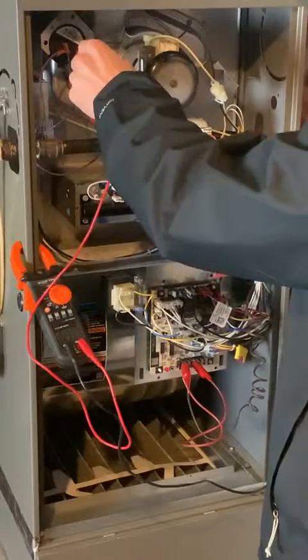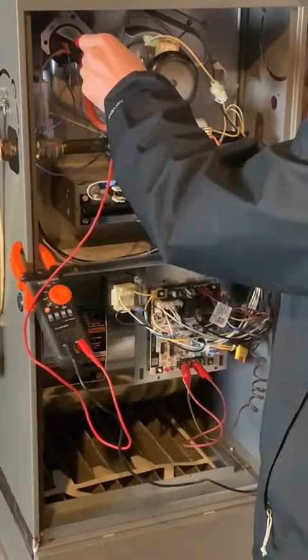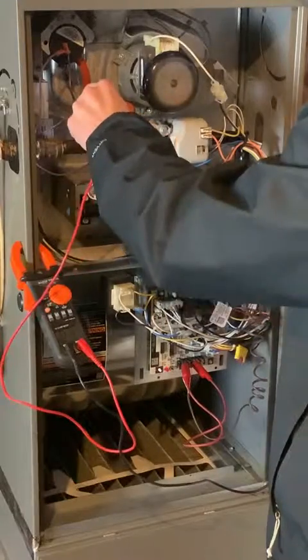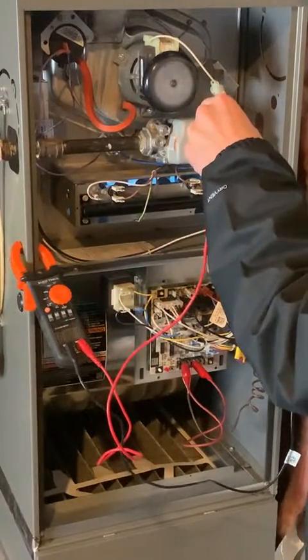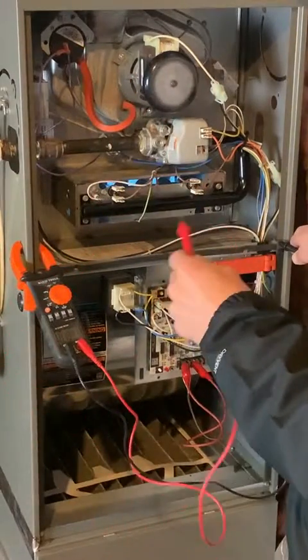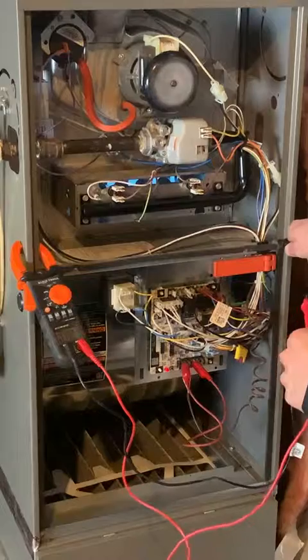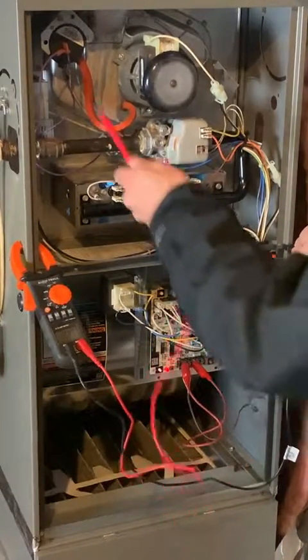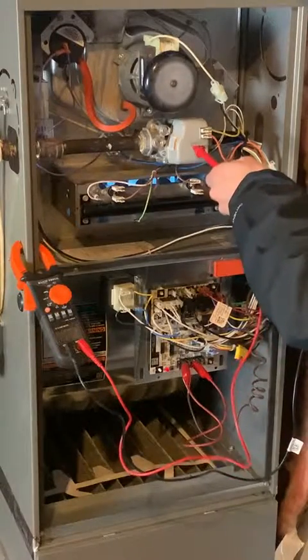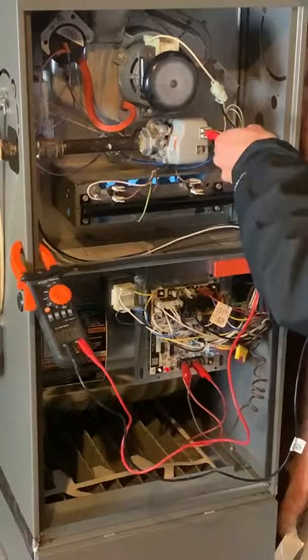If a pressure switch isn't outputting 24 volts, it could mean the switch itself is bad, or it could mean the motor isn't venting properly. We'll go into more depth on how to determine whether it's the sensor that's bad or the component the sensor is monitoring — that's part two of being a technician. You've got to figure out: is it the sensor, or is it the thing being sensed? We'll cover the procedure for that in the next video.